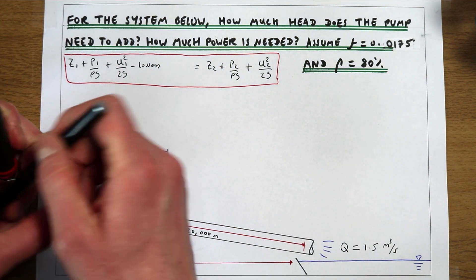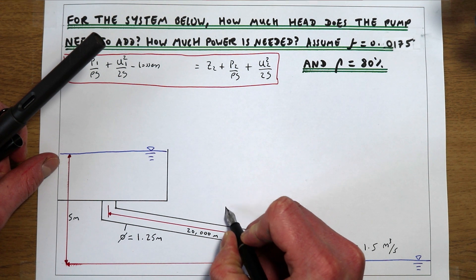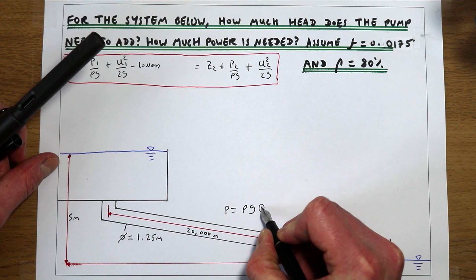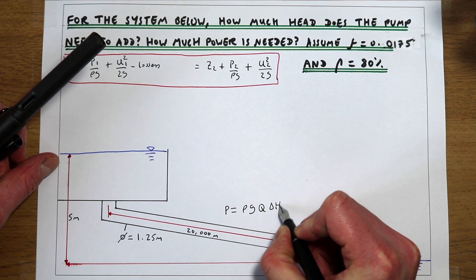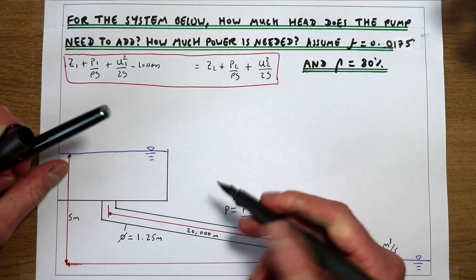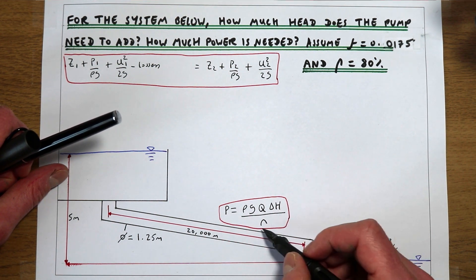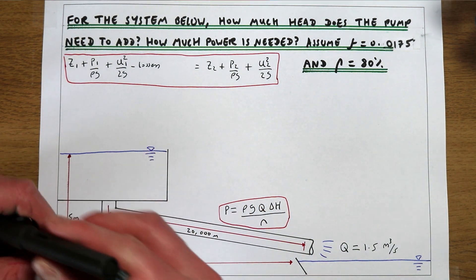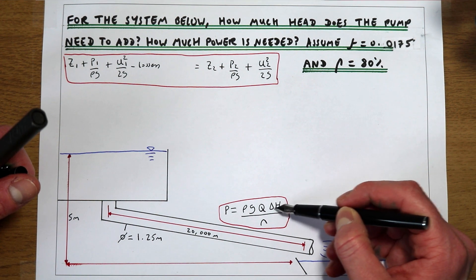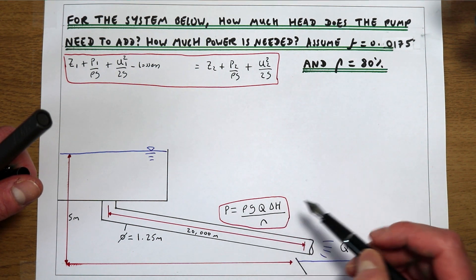The other thing we need to know is how much power a pump requires. The power that a pump requires is the density of water times gravity times the flow rate of the system, times the head that the pump is adding to the system, divided by the pump's efficiency. In this example the pump's efficiency is given as 80%. So firstly we need to work out how much energy in terms of pressure head the pump needs to add, and secondly how much power we need to provide to give that extra energy.